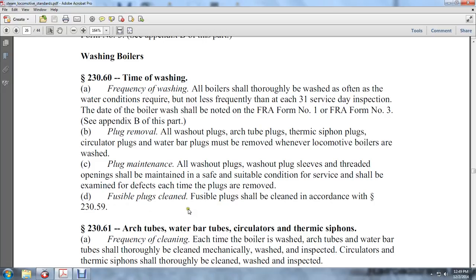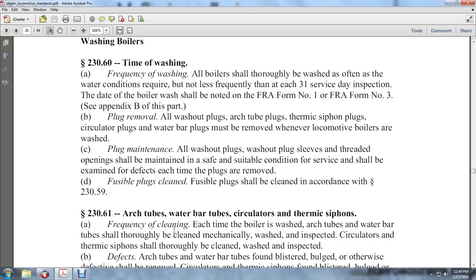Arch tubes, water bar tubes, circulator thermic siphons: at each boiler wash, arc tubes and water bar tubes shall be thoroughly cleaned and mechanically washed. Circulators and thermic siphons shall also be thoroughly cleaned, washed, and inspected for defects.